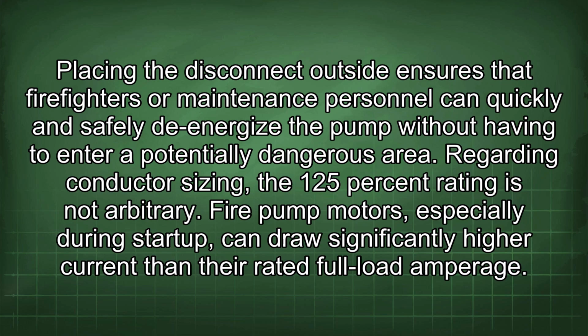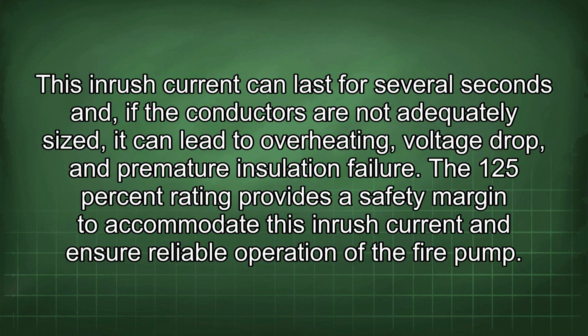Regarding conductor sizing, the 125% rating is not arbitrary. Fire pump motors, especially during startup, can draw significantly higher current than their rated full load amperage. This inrush current can last for several seconds, and if the conductors are not adequately sized, it can lead to overheating, voltage drop, and premature insulation failure. The 125% rating provides a safety margin to accommodate this inrush current and ensure reliable operation of the fire pump.